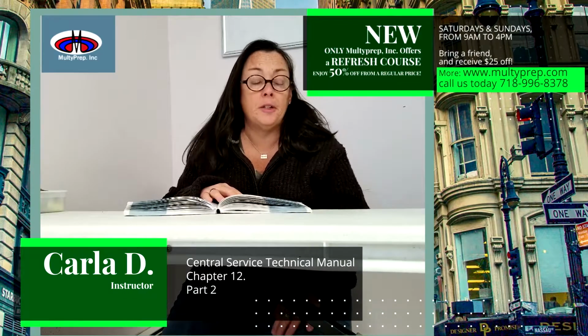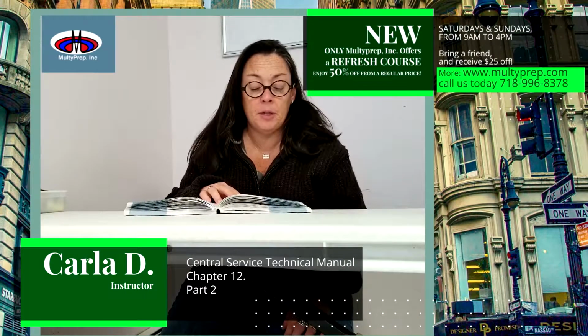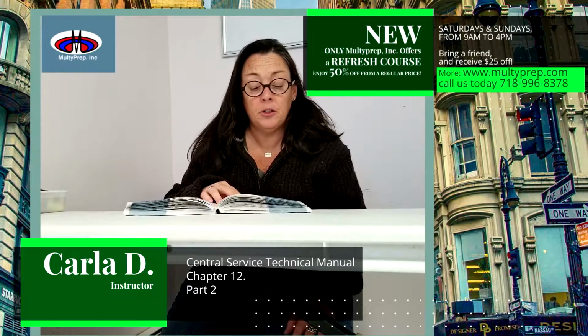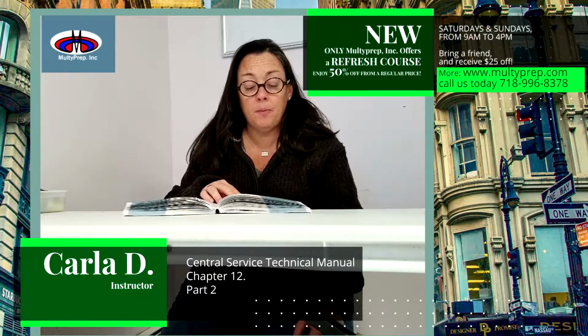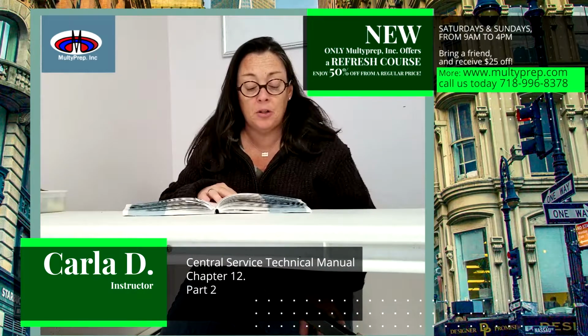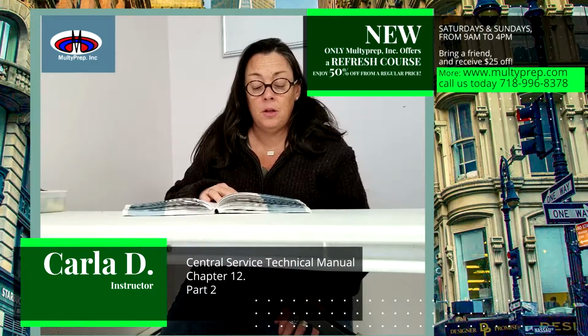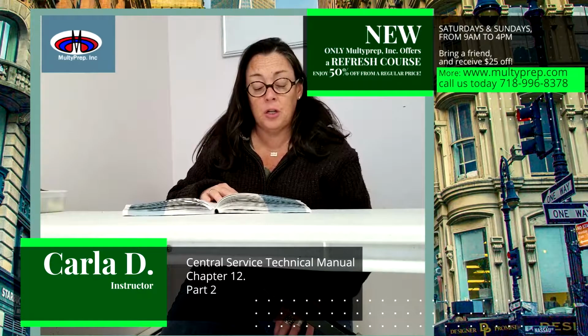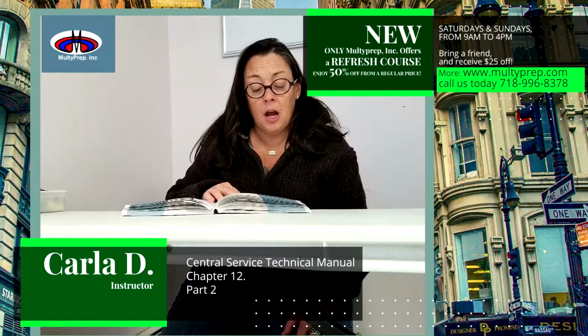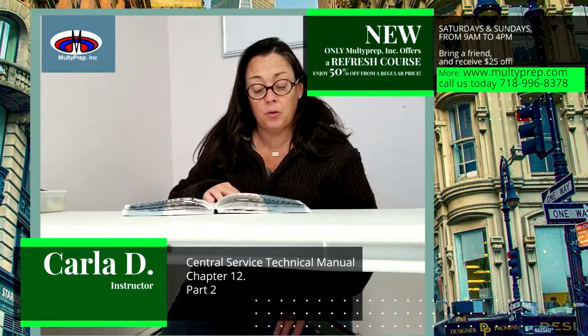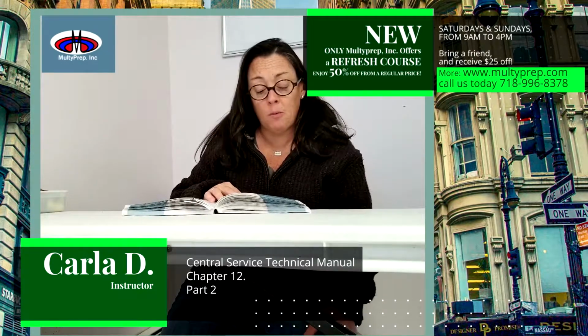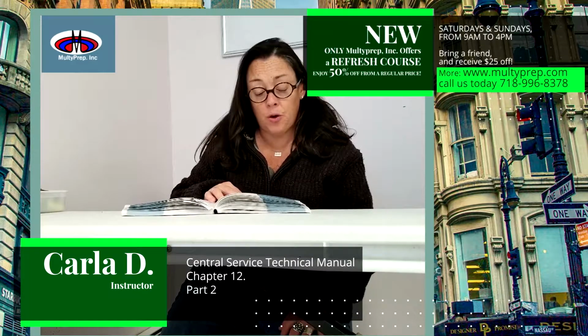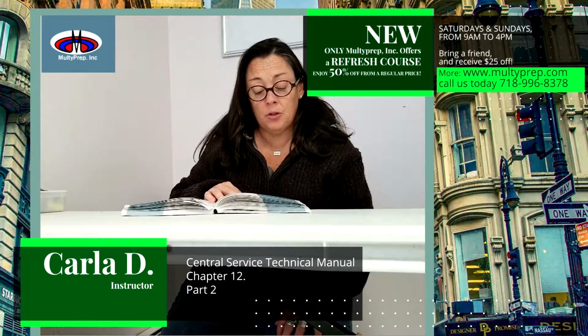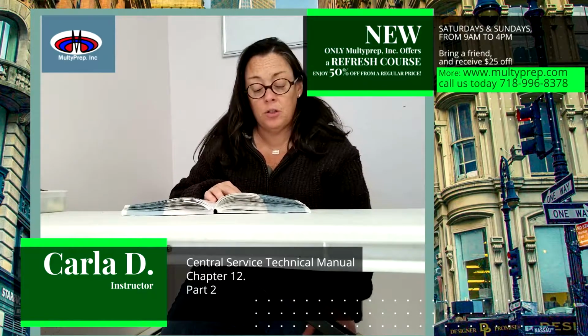Don't create overweight trays. Be aware of tray weight and density recommendations from the manufacturers of sterilizers, instruments, and packaging systems. In addition to possible issues associated with heat-up and drying, excessive tray weight can present ergonomic challenges for those who must lift the trays. ANSI/AAMI ST77, containment devices for reusable medical device sterilization, and ANSI/AAMI ST79, comprehensive guide to steam sterilization and sterility assurance in health care facilities, recommend a maximum weight of 25 pounds for containerized trays. This includes both the weight of the instruments and the instrument container together. See Figure 12.19.